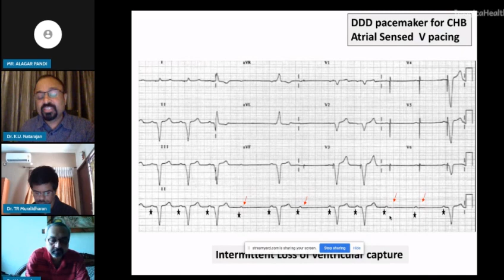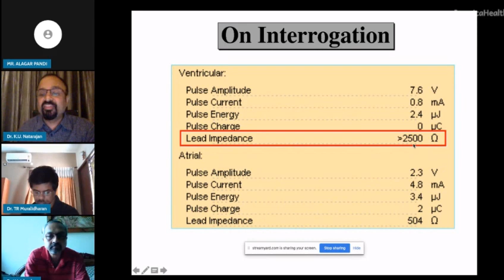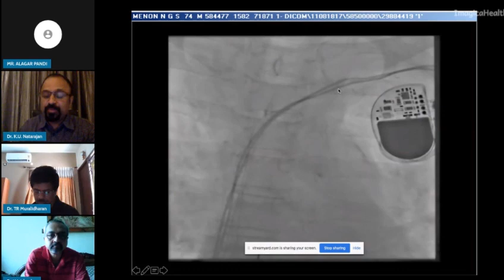I have marked the P waves for you with this asterisk here. The red arrows are those places where the ventricle is not captured. So this is a dual chamber pacemaker where there is intermittent loss of ventricular capture. And if you look at this again, Dr. Jaishankar is going to tell you on these aspects. When you interrogate the device with the programmer, the ventricular lead impedance is very high, 2500, which means there is likely to be a lead failure which is responsible for the intermittent capture loss. And when you do a fluoroscopy, you see that there is a lead fracture of the ventricular lead. So that is the importance of interpreting an ECG.